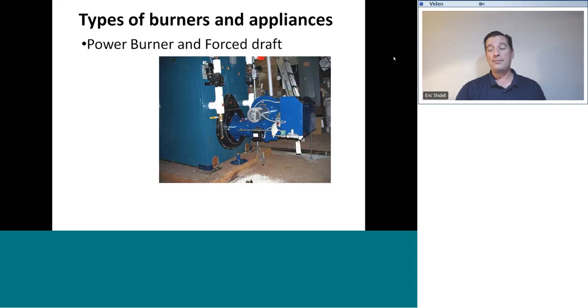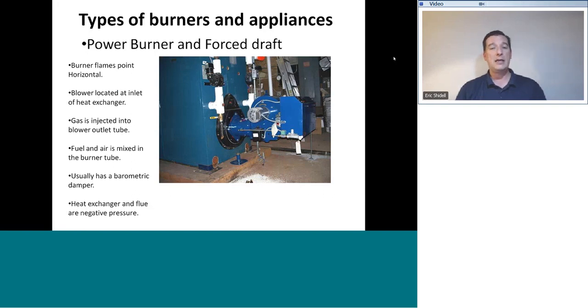A forced draft burner or power burner is also known as a gun burner, and we'll see why in just a little bit. They kind of look like a gun in a way. In a power burner, flames also point horizontally. They don't go up like this. They go horizontally. And there is a blower, and the blower is located at the inlet of the heat exchanger. In our induced draft products, the blower was located on the outlet of the heat exchanger, and it pulled combustion products through the heat exchanger. In our gun burners or power burners, the blower is at the inlet of the heat exchanger, and it discharges into the combustion chamber, essentially blows into the combustion chamber, hence the name forced draft.